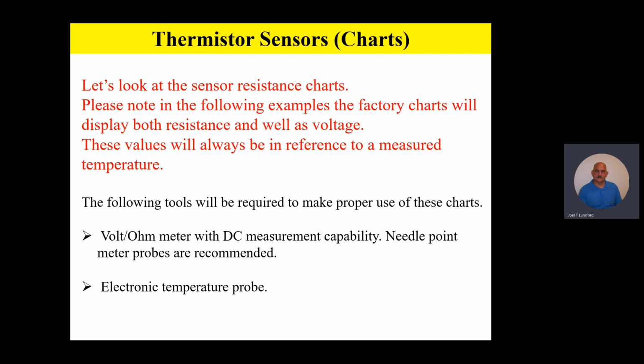And you're also going to need a high quality electronic temperature probe, because there's going to be times you're going to be clamping on to a line. For instance, on the coil sensor, you're going to clamp on your electronic temperature probe where that coil sensor is actually mounted onto the coil outside on the heat pump, and read the temperature of that refrigerant line where that sensor is clamped on. In addition, you're going to want to be able to make accurate readings of outdoor air temperature to accurately measure your ambient or your outdoor sensor. And finally, on some products, we do have a discharge line sensor as well, and you're going to need a good high quality temperature probe to clamp on to that discharge line off the compressor where that sensor is actually located and read the temperature of that discharge line. So you get the idea. You have to have a good quality temperature probe if you're going to make all this work for you. So good tools are definitely recommended.